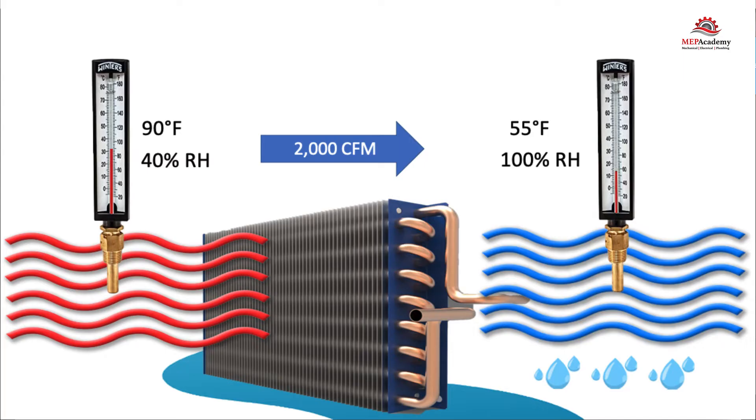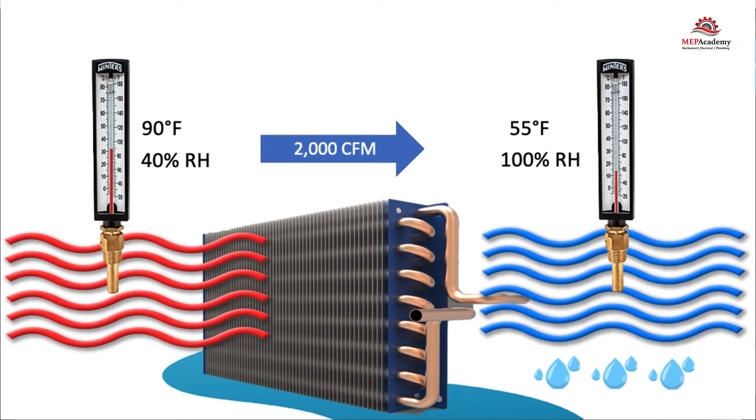Step 2 is to put all the known values into our formula and make the calculation. We have our formula of Q equals CFM times 4.5 times delta H. Now we enter our values.